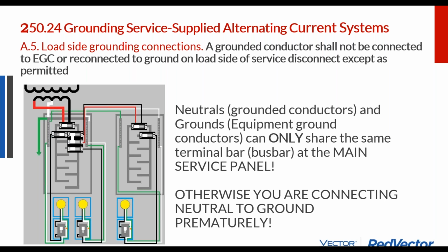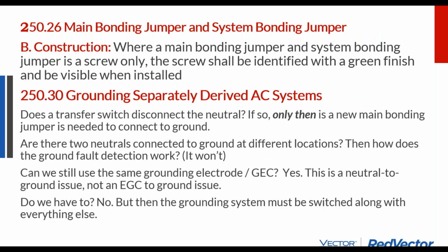So don't just willy-nilly screw in the green screw and ground the service panel because it's there. You have to ask, am I building a brand new service and I need to establish that neutral to ground connection at one spot, or has it already been done for me?